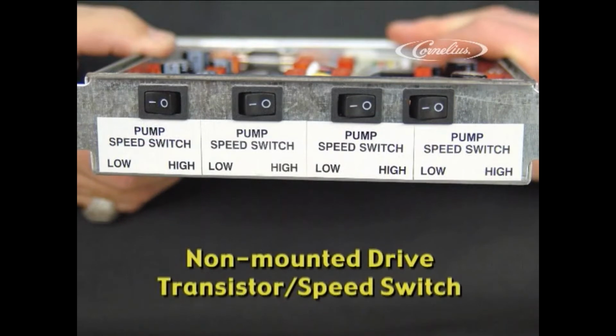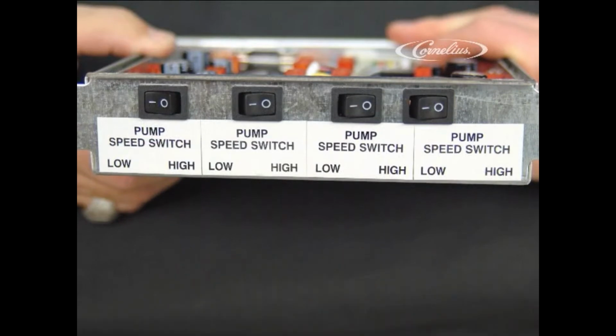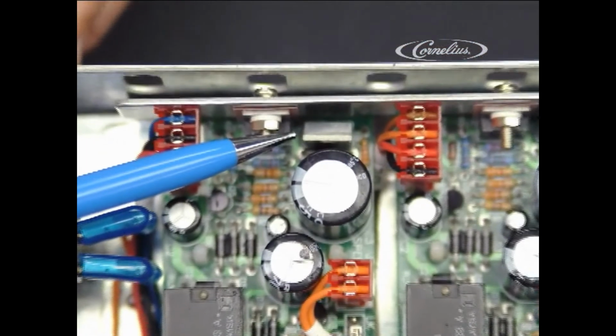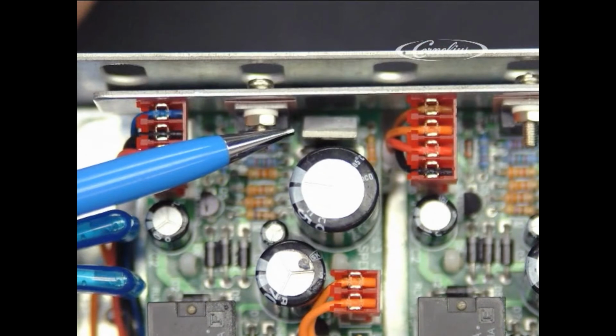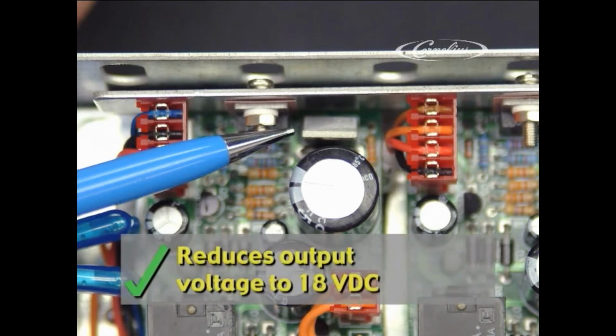The VRB board comes with the ability to do a lower speed. This is accomplished by placing in series with the primary and mounted drive transistor a second transistor. When the speed switch, mounted to the front of the electrical box, is placed in the low position, it engages the second transistor into the circuit. After initially starting at 32 volts DC, in a millisecond, the second drive transistor removes approximately 10 volts DC from the circuit, thus producing an output of approximately 18 volts DC. Since all the heat is in the primary, we do not need to draw heat from the secondary transistor.